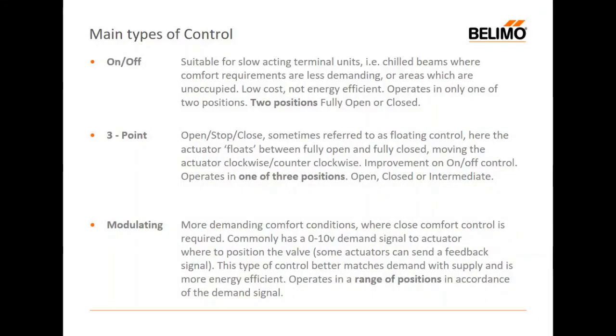So we should look at the main types of control that are utilised in this region, and I'll just run through these if I may. The first is on-off control. We still see it in some of the older buildings and sadly in some of the new ones too. This is a very simple form of control. It's low cost. It's not terribly energy efficient, but the control valve assumes one of only two positions. Fully open when demand is required, when cooling is required, the valve goes to the fully open position and gives everything that is available. And then when the cooling condition is satisfied, the thermostat is tripped, we now start to close the valve. So we're giving all or we're giving nothing.